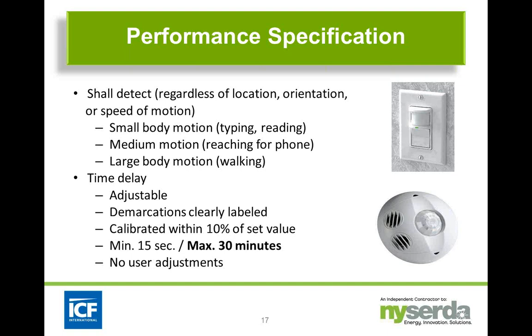Again, with the commissioning process, you want to make sure you set your minimum appropriate to the type of activity in the space. And the maximum, again, shouldn't be any higher than 30 minutes, and this is set by the ASHRAE standards. You also want to have no user adjustments, especially with the wall-mounted occupancy sensors. NYSERDA does offer incentives for installing wall-mounted occupancy sensors, but there's a stipulation that you cannot disable the automatic off feature. So you want to make sure that these user adjustments for time delay and automatic off are not readily accessible to the general public.